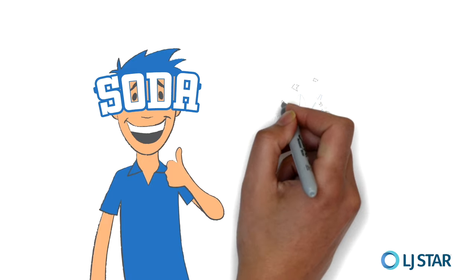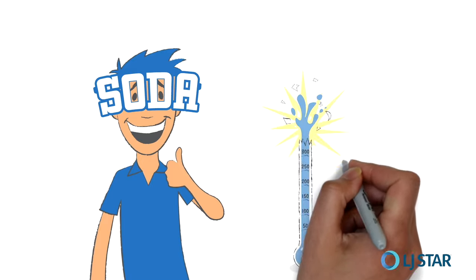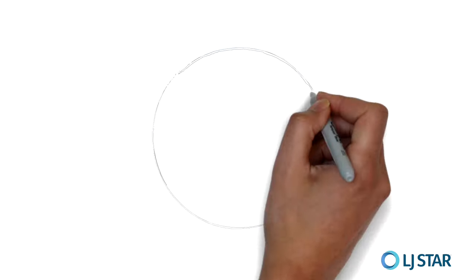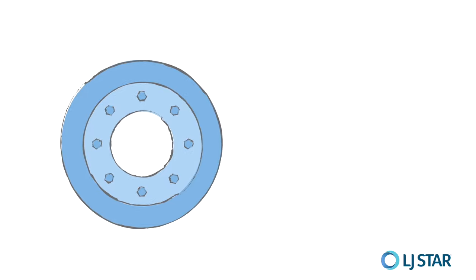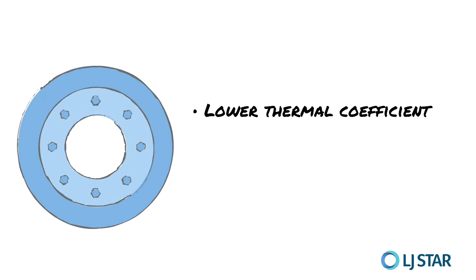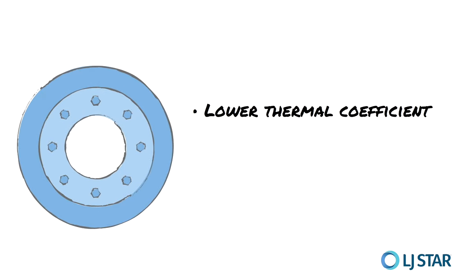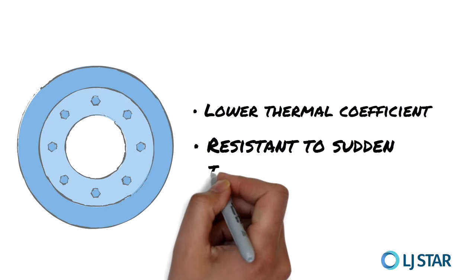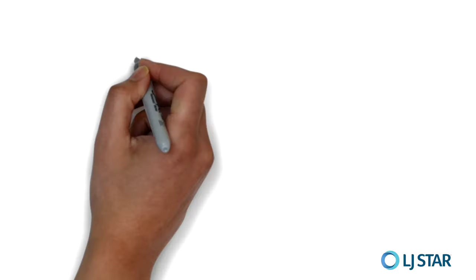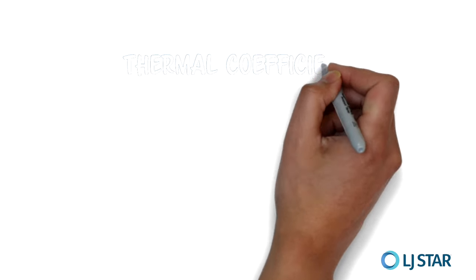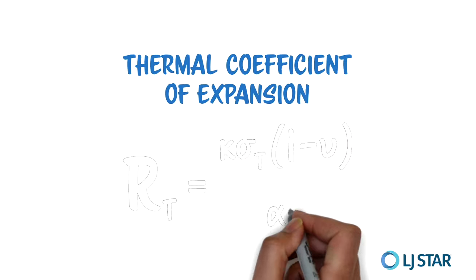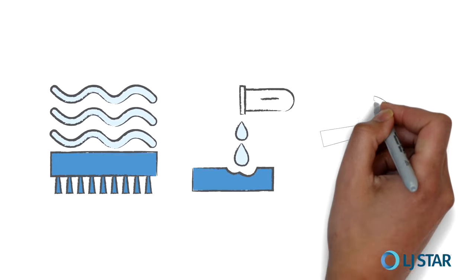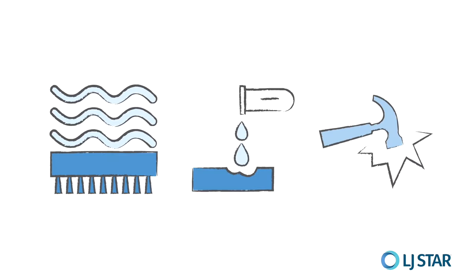Next, consider whether your application will subject the sight glass to thermal shock, like we saw in that Consumer Reports video. If so, genuine borosilicate glass should be specced. That's because borosilicate glass has a considerably lower thermal coefficient of expansion than soda lime glass, making it more resistant to sudden temperature changes. There's real science behind this — there's even a formula for it — and I'll show you where you can look this up later.